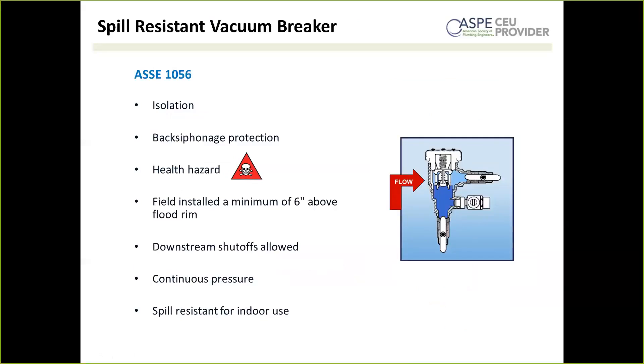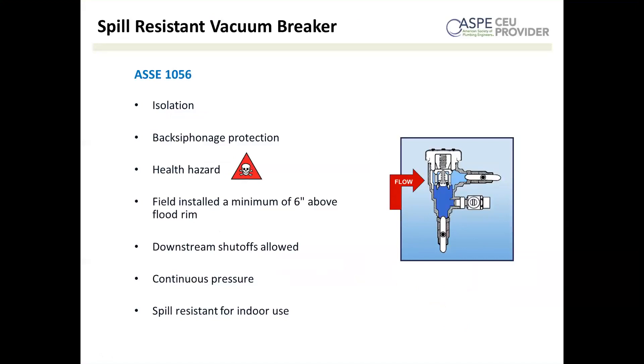A spill-resistant vacuum breaker, ASSE 1056, operates largely the same way as a pressure vacuum breaker, but has a spill-resistant feature that closes the vent prior to the check opening, allowing water to fill the device. This makes them appropriate for indoor use, where occasional discharge from a standard pressure vacuum breaker is more objectionable — you don't want water on the floor. You'll find them in applications such as indoor chemical dispensers, like soap dispensers or cleaning chemicals for mop sinks.